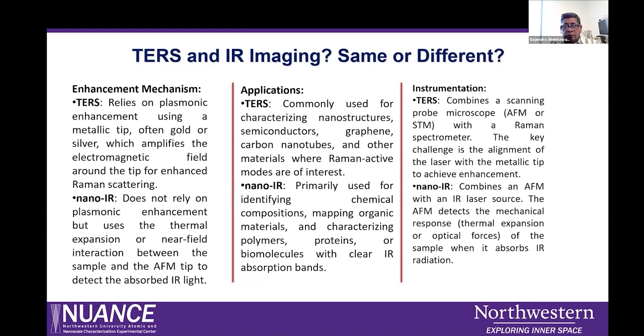TERS, as I said, can be used for nanostructures, semiconductors, graphene, carbon nanotubes. TERS has a limitation that the sample thickness has to be just a few nanometers. So sample prep is very critical in the case of TERS mapping. In the case of nano IR, there is no limitation as such. The depth resolution can go up to 100 nanometers with contact mode. Tapping mode IR imaging is more surface sensitive. It is not limited to just semiconductors. You can do a lot of proteins, biomolecules, and polymers, because most of these proteins and polymers nicely absorb IR. So that's the difference here.